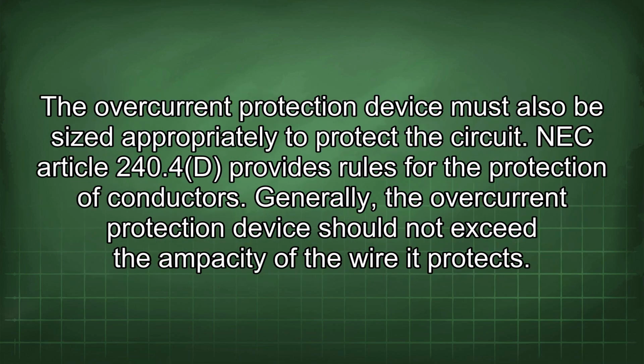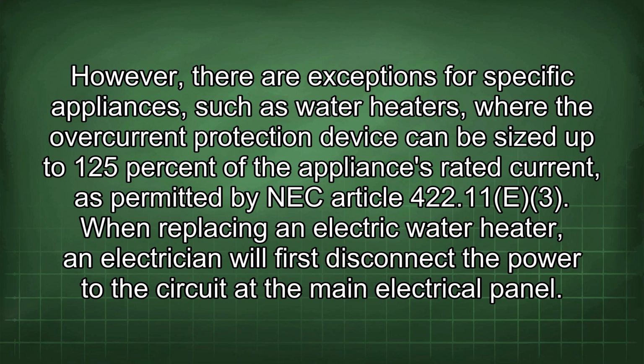The overcurrent protection device must also be sized appropriately to protect the circuit. NEC Article 240.4(D) provides rules for the protection of conductors. Generally, the overcurrent protection device should not exceed the ampacity of the wire it protects. However, there are exceptions for specific appliances, such as water heaters, where the overcurrent protection device can be sized up to 125% of the appliance's rated current, as permitted by NEC Article 422.11(E)(3).